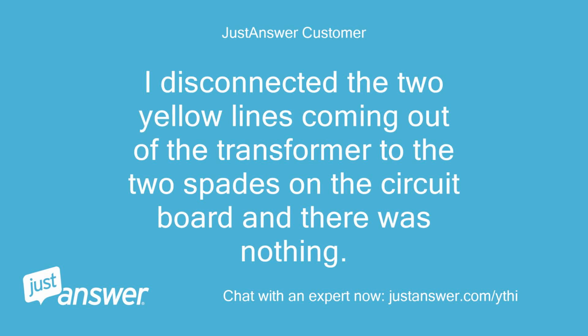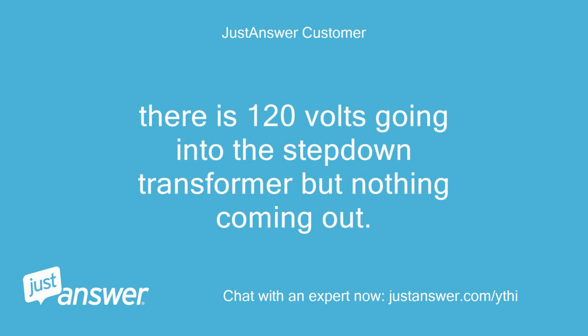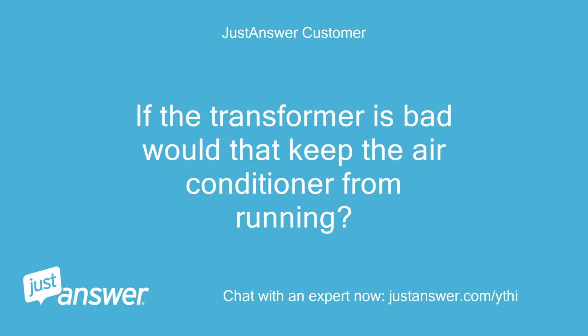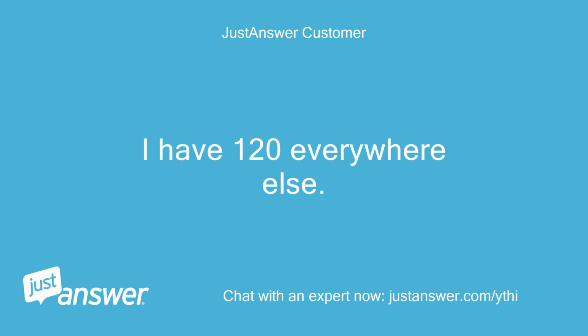I disconnected the two yellow lines coming out of the transformer to the two spades on the circuit board, and there was nothing. There is 120 volts going into the step-down transformer but nothing coming out. If the transformer is bad, would that keep the air conditioner from running? I have 120 everywhere else.